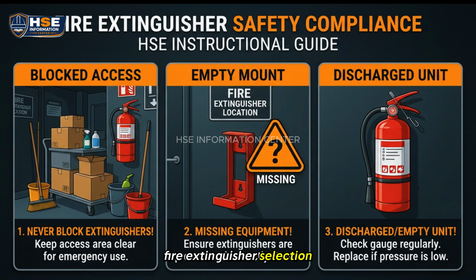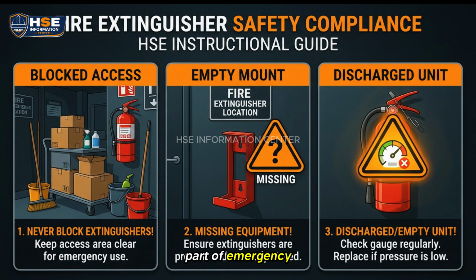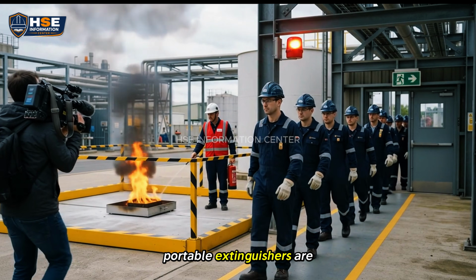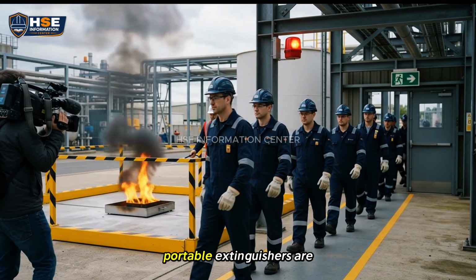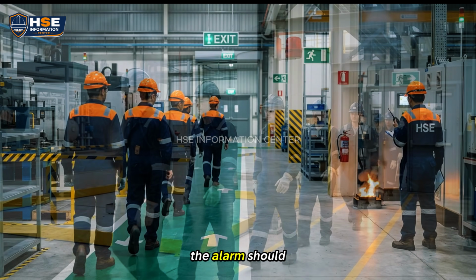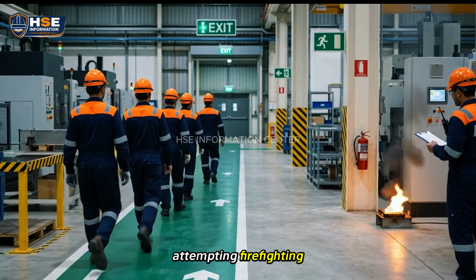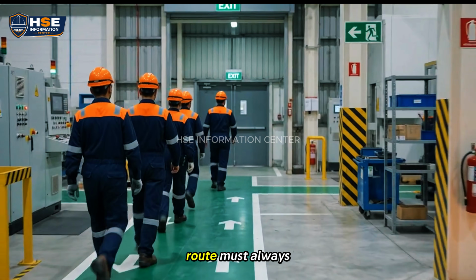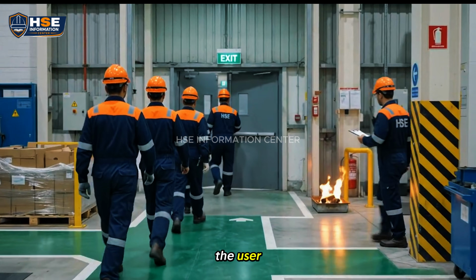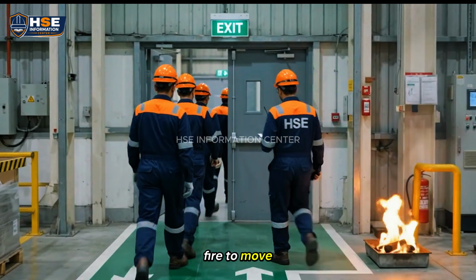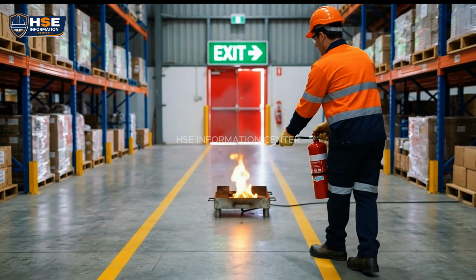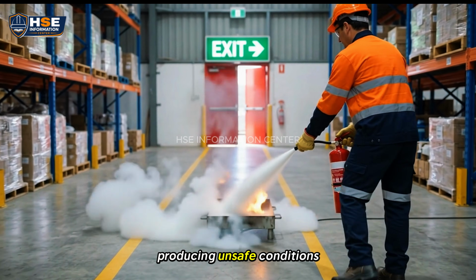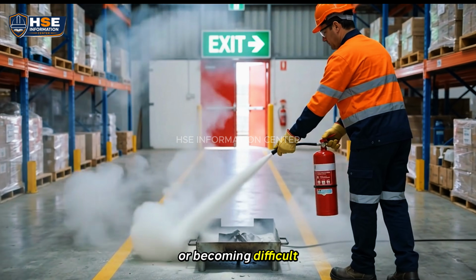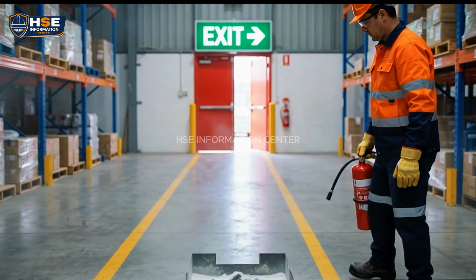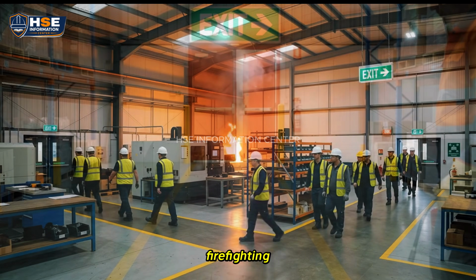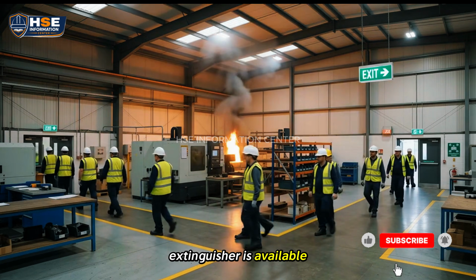Fire extinguisher selection is only one part of emergency response. Portable extinguishers are intended mainly for small, early-stage fires. The alarm should be raised before attempting firefighting. A clear escape route must always remain available behind the user. Never allow the fire to move between you and your exit. If the fire is spreading, producing unsafe conditions, or becoming difficult to control, evacuate. Do not continue firefighting simply because an extinguisher is available.